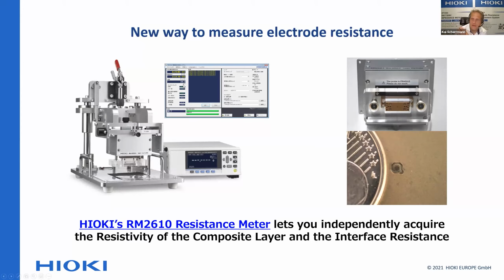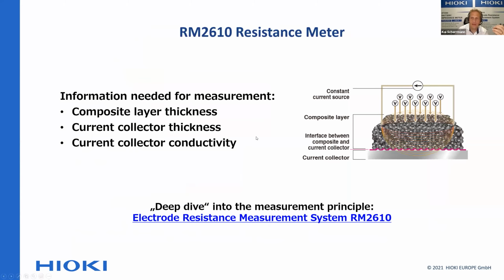These multiple probe tips allow you to make multiple measurements, then take these measurements, put them into a 3-dimensional mathematical model, and do a calculation. The outcome is the value for the interface resistance and the value for the composite resistivity. So it is possible to get separate values for that. You only need three pieces of information that you feed into the system: the composite layer thickness, the current collector thickness, and the current collector conductivity.